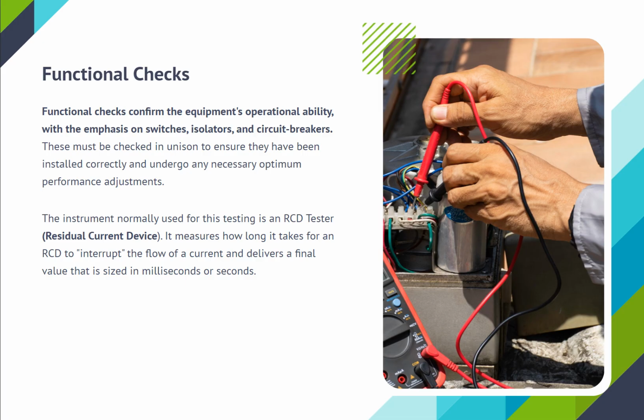The instrument normally used for this testing is an RCD tester, residual current device. It measures how long it takes for an RCD to interrupt the flow of a current and delivers a final value that is sized in milliseconds or seconds.